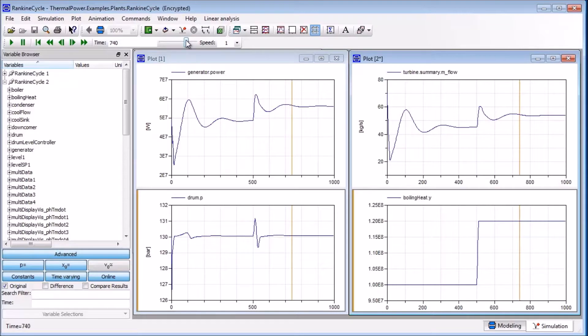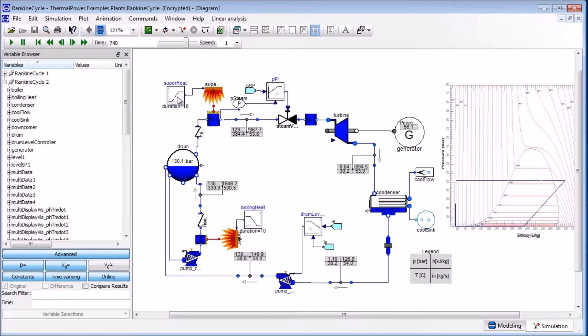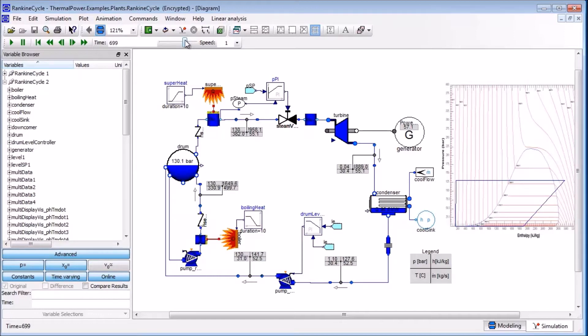Now we will look at the diagram view. We close the plots and return to the system diagram view, where it is possible to zoom in and out. To visualize the animation, click on the green arrow to start it. It is possible to specify the speed of the animation — for example, faster or slower than real time. Alternatively, you can manually drag the slider and see directly on the diagram how the level in the drum and condenser changes. The model also visualizes the working process in the p-h diagram, and pressure, enthalpy, temperature, and mass flow are displayed at various locations in the system.